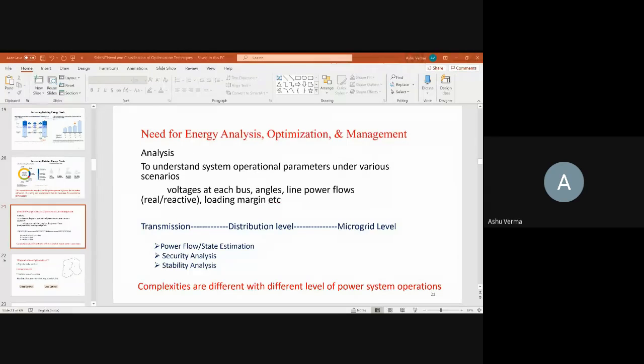So to increase that voltage, you may look into voltage support options, how you can increase that voltage. If it is a transmission system, voltage is primarily impacted by reactive power exchange. So you may try to give reactive power which is required by the system so that voltage can come up. That reactive power support can be given by some nearby synchronous generator, where you can change its voltage setting, and because of that the excitation current can be changed to give that terminal voltage, and overall the reactive power exchange can be changed. That is one option.